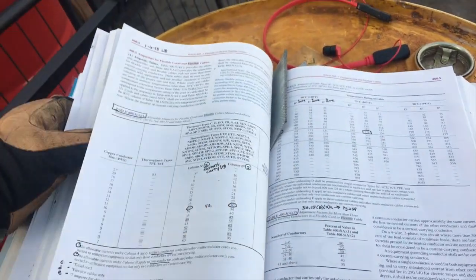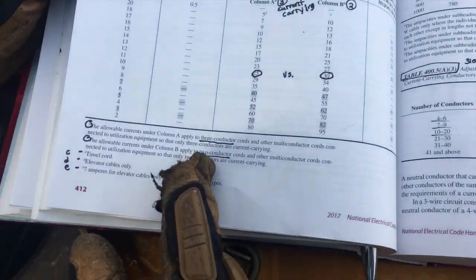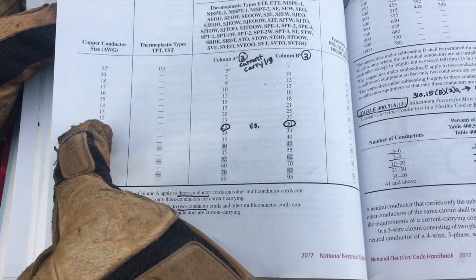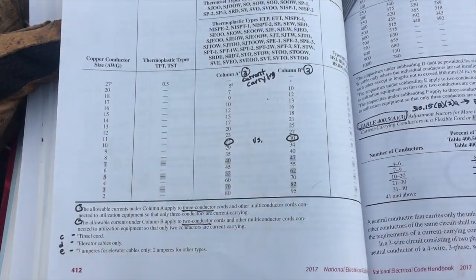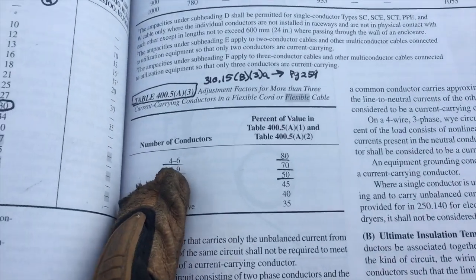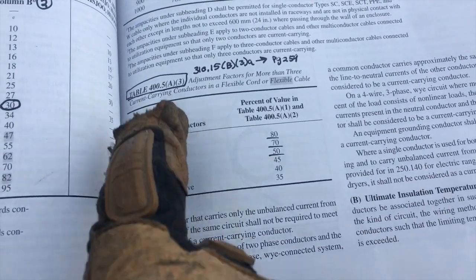So in our case it was rated for that. Then we come over to here and see that a B rating for two conductor is going to be in this column here, and at a 12 gauge is good for 25 amps. You can also check in here how many number of current carrying conductors if you get a bigger cord than that.